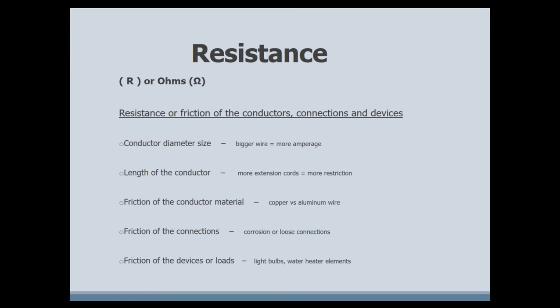What about if you tie two or three extension cords together? All of a sudden, what does that do to the pressure being applied to those electrons? It may have been fine going into that first extension cord, comes out a little decreased, but by the time it comes out of the second extension cord, you may have dropped some voltage, because of the length and also the diameter. It's nothing unusual to see 115 volts going into that extension cord, but by the time you run, say, 200 feet of extension cord out there, you may be down below 100 volts on the other end of that cord.